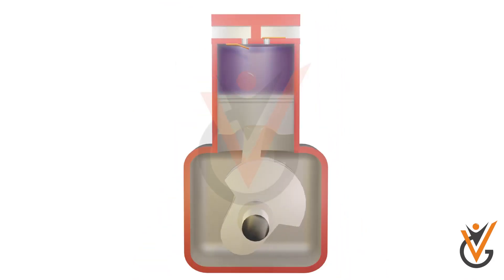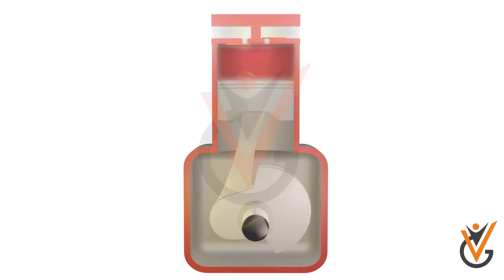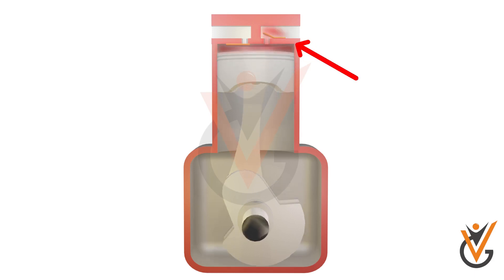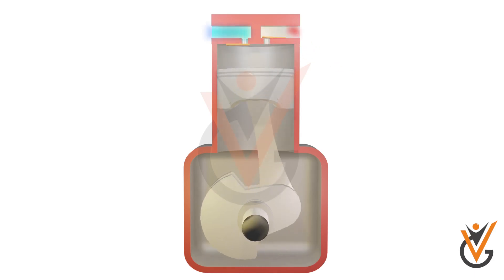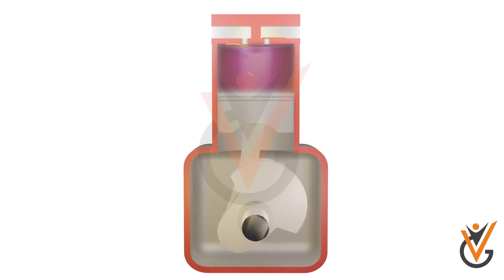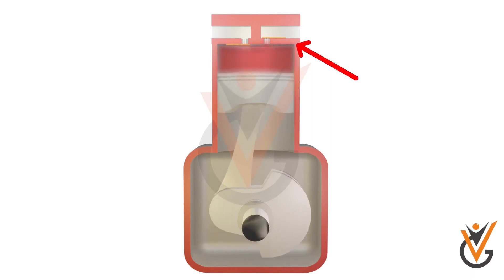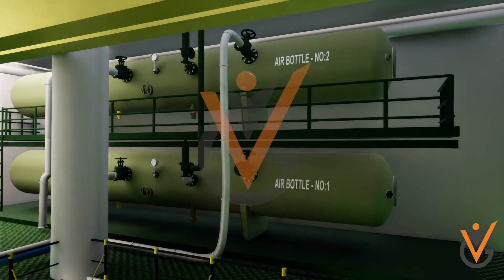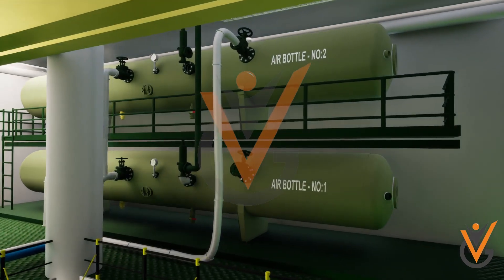Now the piston reciprocates upward, and this upward movement starts building up the pressure and closes the suction valve. When the air gets pressurized to its specific value, the discharge valve gets opened and the pressurized air starts moving through the discharge line and gets stored in the air bottle.